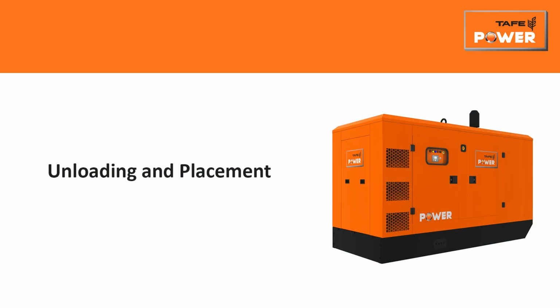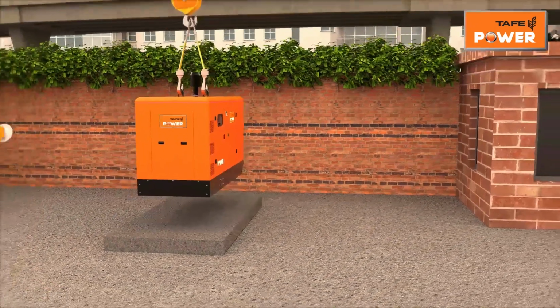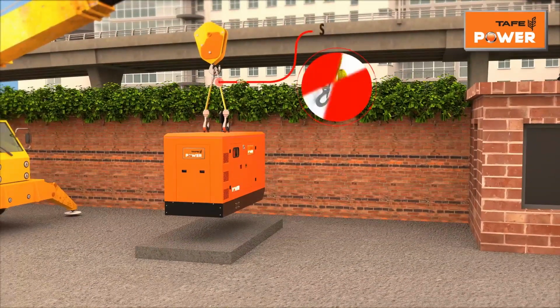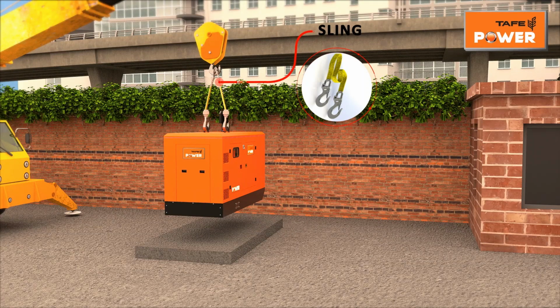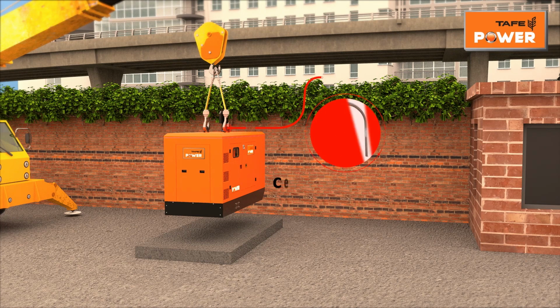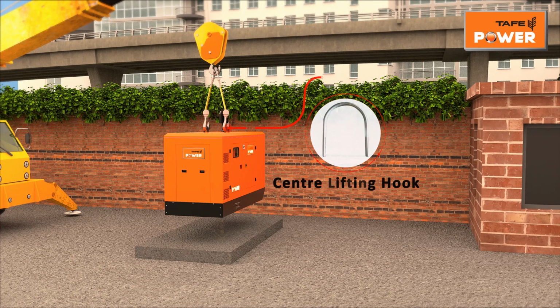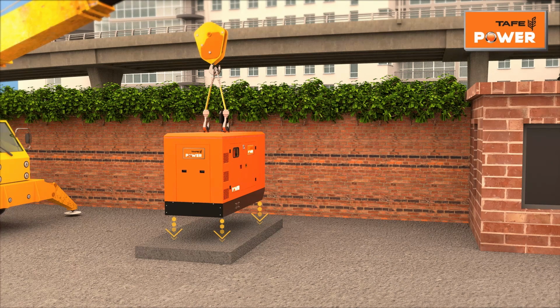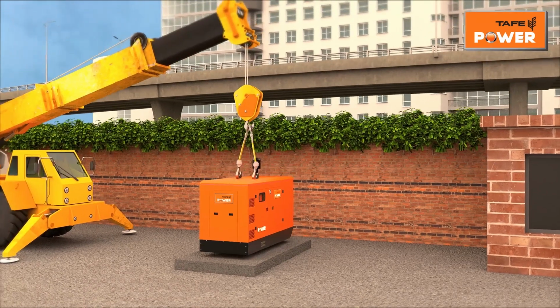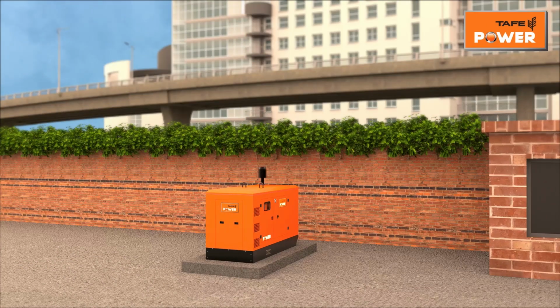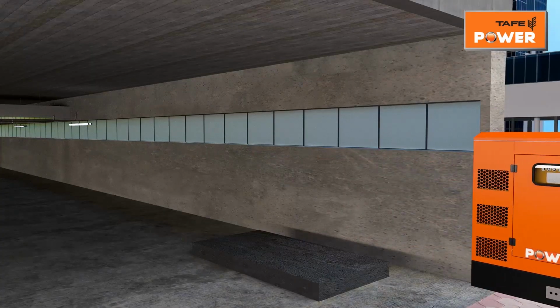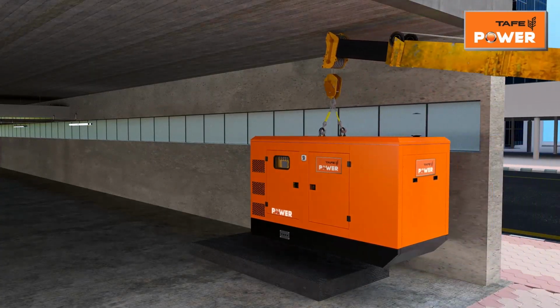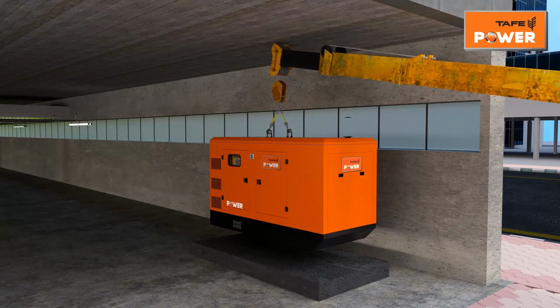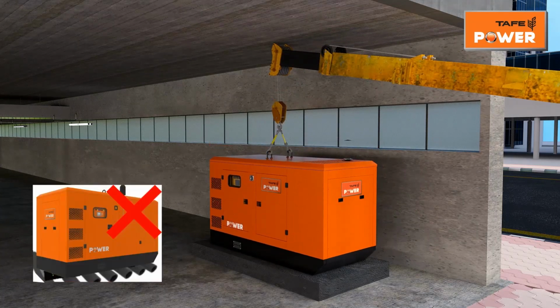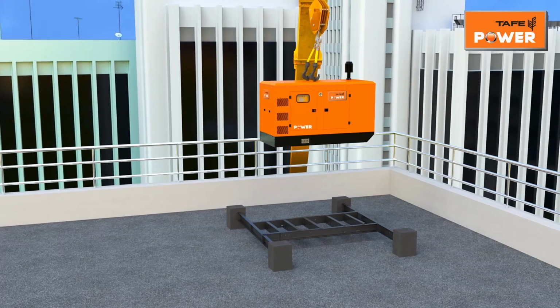Unloading and placement. Unload the genset by using proper lifting tackle with nylon sling or soft sling of suitable capacity to avoid any damage. Use center lift points on the canopy which provide support to the equipment when it is moved. Genset should be placed exactly in the middle of the foundation. Ensure suitable distance from genset for safety. Avoid rolling of genset through pipes as it can damage base rail. Place genset on rooftop with proper care.